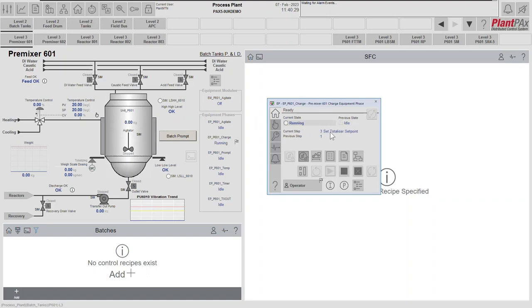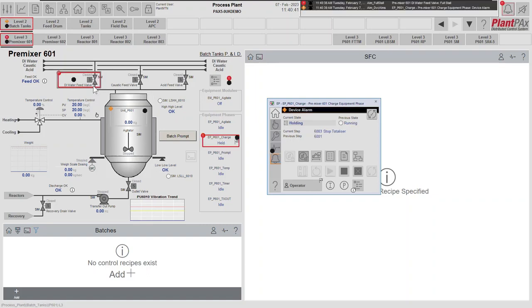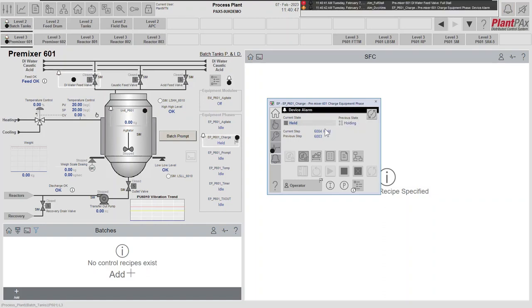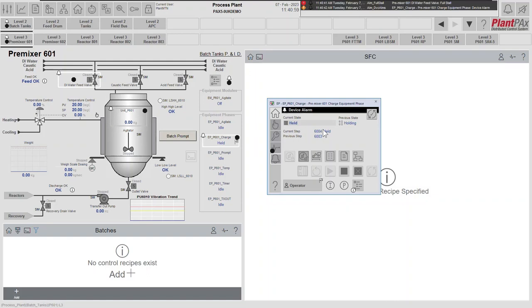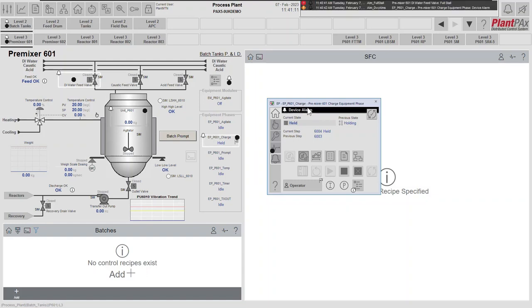We can then see the steps as the phase is running - we're starting the totalizer, and now the phase sequence has gone on to trying to open the DI water valve. The valve has been commanded but has failed to move, and we can hear the alarms from that valve. It may not be immediately obvious to the user which fault caused the sequence to fail. The sequence has failed, gone into hold, and is showing a device alarm. But this is where the nice feature of Organization, Ownership and Arbitration makes it very easy for the user to identify the devices that are causing an issue for this equipment phase.